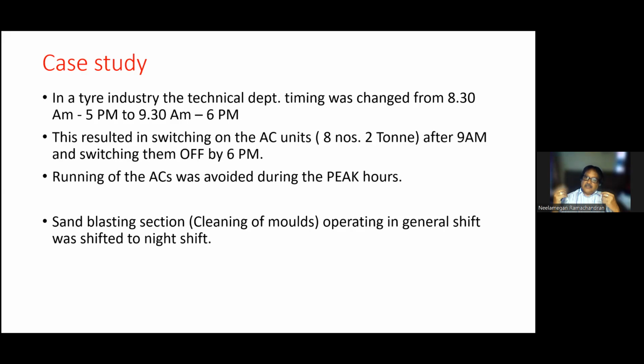Same thing, there was a sand blasting section where they clean the mold by blasting sand. There were huge blower motors there. These people would come in the general shift, clean the mold and keep it ready for second shift and third shift usage. What we did was change the timing to night shift. Only in the night shift do they use shot blasting. So by doing that, the blower motors were running only during the night, where the tariff was low.